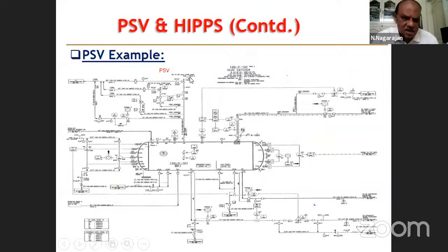So this is the equipment, PSV. I think it may be legible to some extent. This is the separator vessel with liquid inside, and you have the gas phase. This is the gas outlet. And there is a pressure safety valve independently mounted on the vessel. It is a mechanical device. Most of the time we put two parallel valves. One will be online always, and the other one has its inlet closed and outlet always open, releasing to the flare. This is a typical safety valve, PSV.